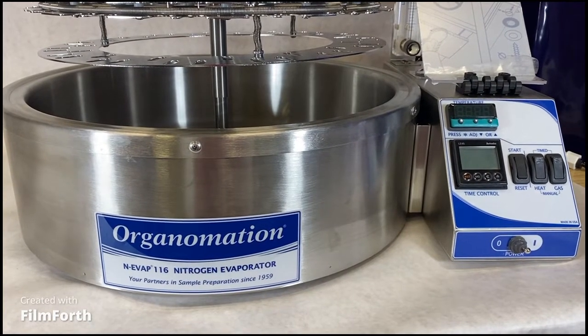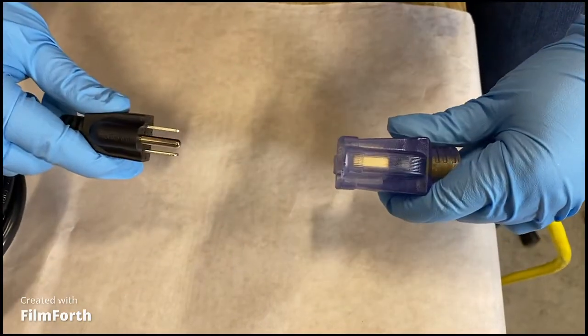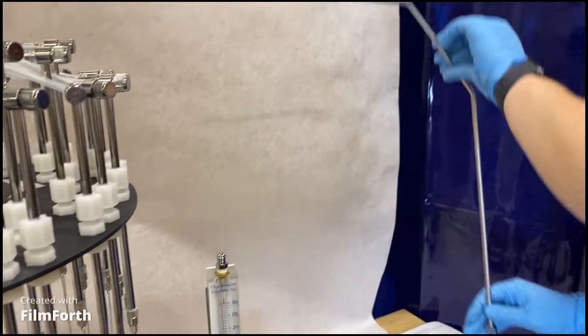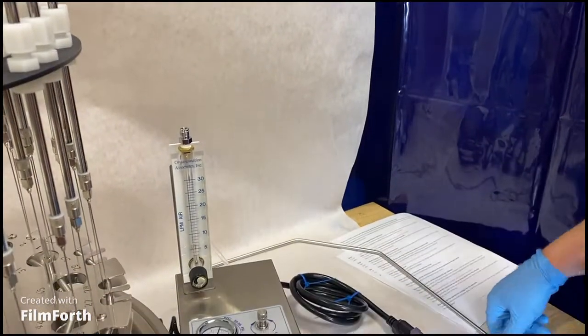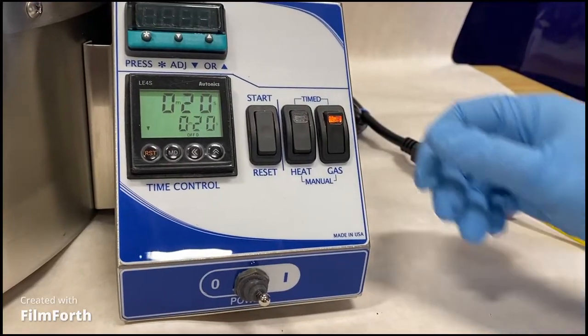For baths manufactured before 2019, check that the gas switch is not stuck internally. Unplug your instrument and let cool before handling. Remove the nitrogen distribution assembly and flow meter.